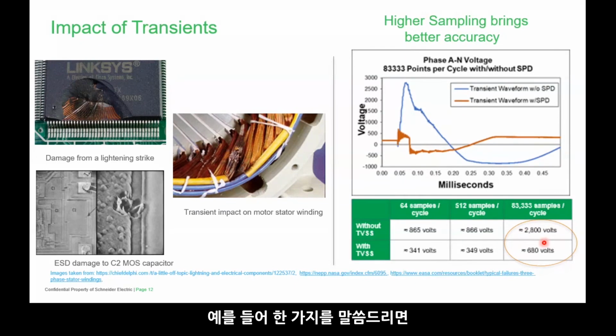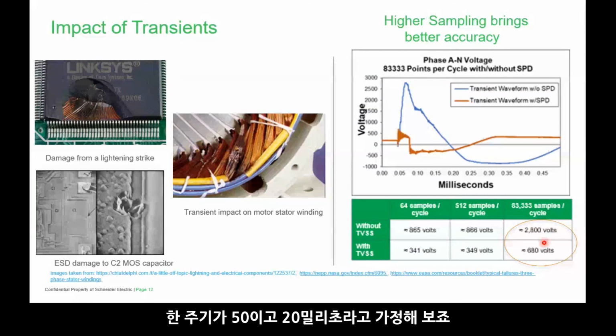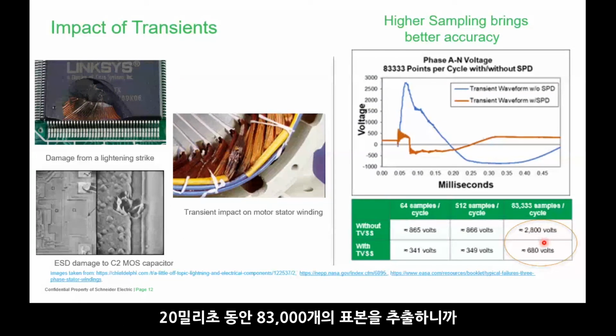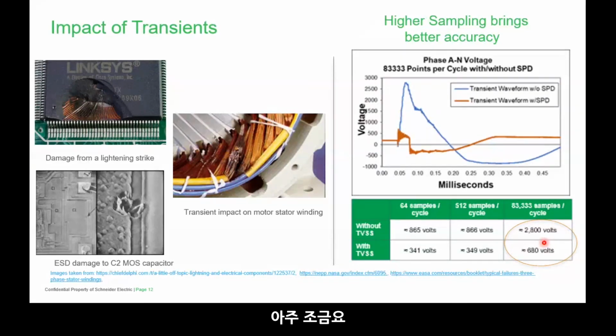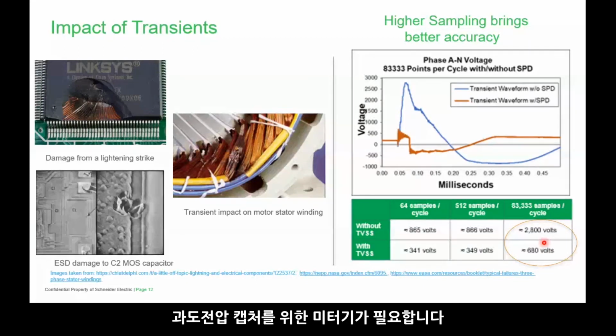So this is just giving you a heads up. One of the key things to take note of is the high sampling rate per cycle. Imagine one cycle at 50 Hz is 20 milliseconds. In 20 milliseconds, you have 83,000 samples. So there's a very slim chance that you will miss any peak voltage on a transient. But if you have a lower sampling rate, then perhaps between one sample and the next another peak may come out, and you may not be able to capture it. So you really need the right meter to capture transient.